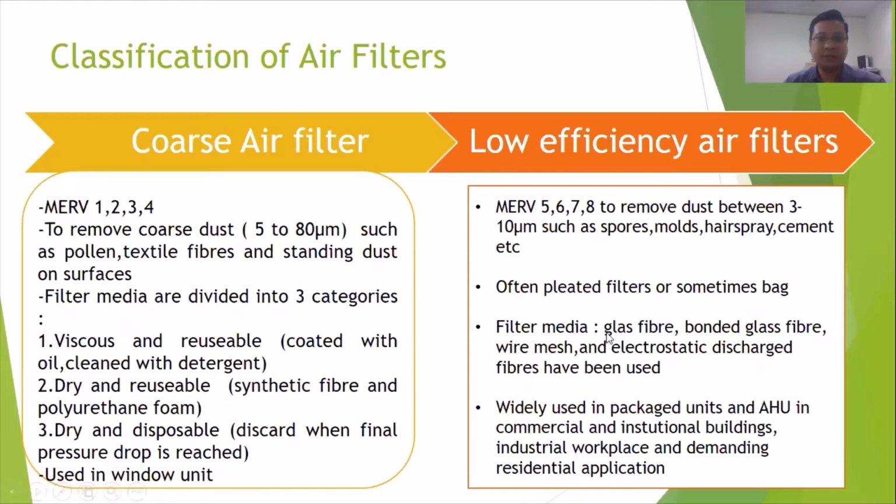The media using glass fiber, bonded glass fiber, wire mesh, and electrostatic discharge fiber are used as the material in the low efficiency air filter level. It is widely used in package units and AHU in commercial and institutional buildings, industrial workplaces, and demanding residential applications. So I think this one is more commonly used in general buildings.